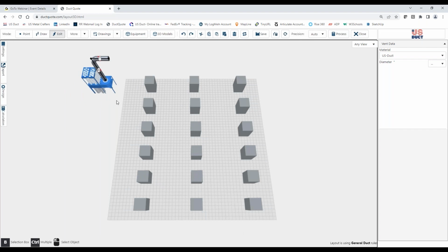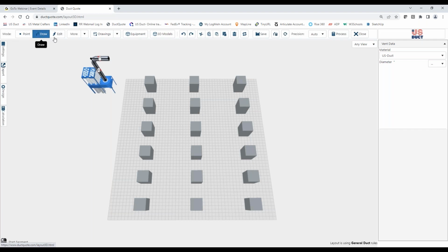Now, we can do this in several ways. Now, typically we think the straighter the path along the trunk, again, the lower the fan pressure. But we also have to remember that more branches equals more fan pressure. And what do we mean by branches? Well, most people understand that. And let's just get that. There we go. All right.